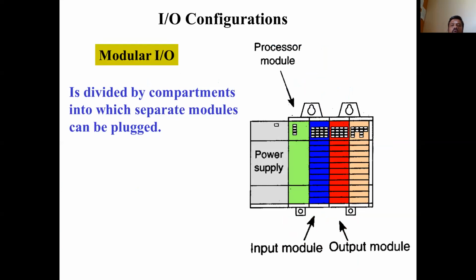Coming to the modular IO, that is an industry type PLC. This is also called a rack type PLC, and it is provided with many racks. Normally the power supply is the first rack, followed by the CPU, that is the processor module. Then it is followed by the input output modules. Generally, it will have analog input, analog output, digital input and digital output modules, and there will be an expansion module, so it can be expanded if you want another module.